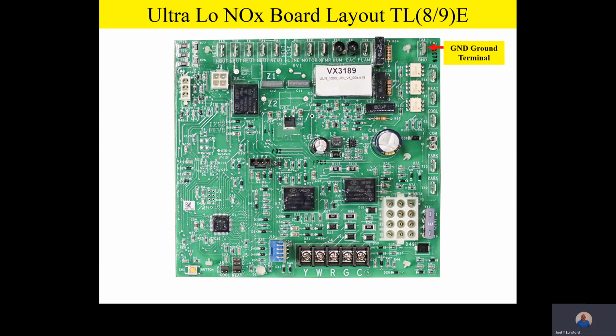As we move over to the upper right-hand corner of the board, we see we have a ground terminal. It should be noted this ground terminal will be referenced to chassis ground. So it's a separate ground terminal on the board to ensure that we have a really good ground on the board. Now, please remember this. You have to have a good solid ground in order for the flame sensor to work properly. As a matter of fact, the number one cause of low flame current, or a problem with the flame sensor, is poor grounding. So please remember that. It's very, very important. This board has to be grounded, and it has to have a good, clean, solid ground all the way back to the power panel for the furnace to work properly.